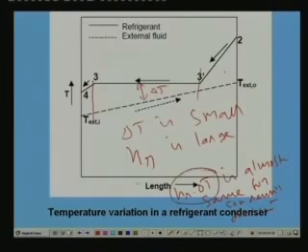Since HR into delta T is almost the same, the area required per watt of heat transfer will also be the same. So, we justify saying that we can neglect the desuperheating phase, and we can also assume that during this phase also the temperature remains constant, and the heat transfer coefficient during the desuperheating region is equal to the condensation heat transfer coefficient.